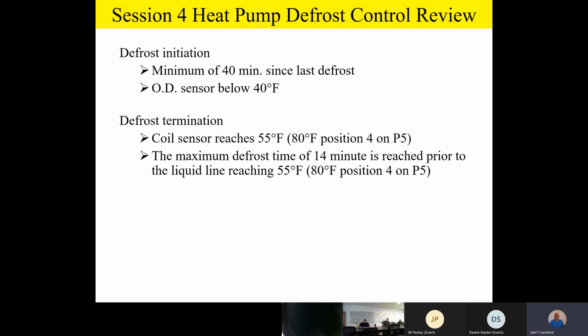So some of the things I'd like everybody to write down or at least put in your memory: as far as our demand defrost control is concerned, you're going to have a minimum of 40 minutes since the last defrost. The reason we do this is if you have a bad sensor, you don't want to just be cycling back and forth between defrost cycles and not getting any work done. So there's a minimum of 40 minutes since the last defrost.